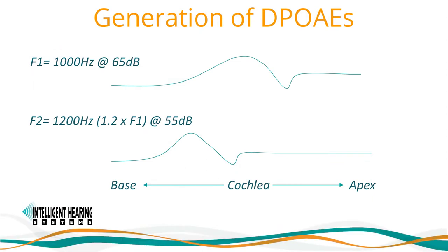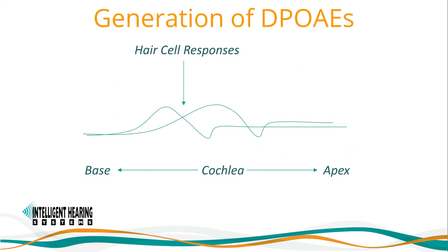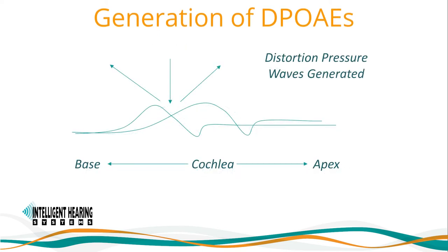Next, the test will begin. DPoAEs are generated by stimulating the cochlea with two frequencies at two intensities, where F2 is 1.22 times F1, and where F1 is typically delivered at 65 dB SPL while F2 is delivered at 55 dB SPL — 10 dB apart. As the signals overlap, hair cell responses generate. These are referred to as distortion product pressure waves, with the strongest intermodulation distortion product emission in the cochlea being generated at 2F1 minus F2, as shown on the frequency spectrum.